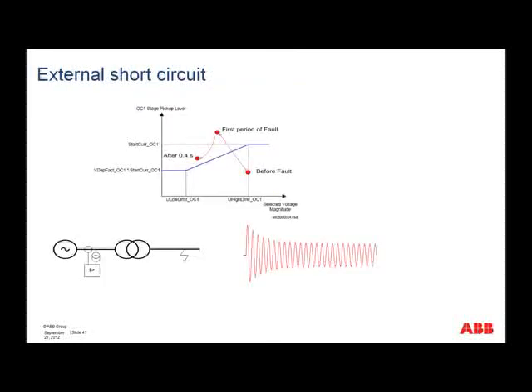So let's look at what happens if we have a short circuit that is fed by generator current. Before the fault, we would be sitting here at the 1 per unit voltage point, and you can see for 1 per unit voltage, the load current would be with good margin below the pickup threshold of the overcurrent function. But then the fault occurs, and initially we have reasonably high fault current. The voltage, of course, will decrease, and so the fault current would be easily above the threshold. But of course, this is not an instantaneous trip. We are wanting to trip after some time delay.